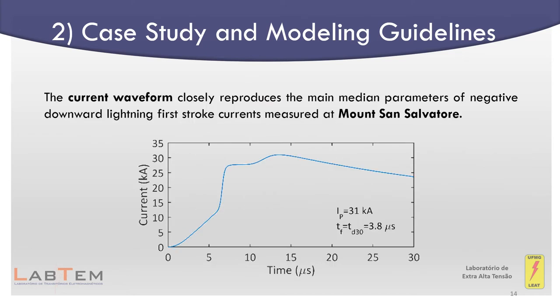The current waveform shown in the figure has been adopted in the simulations. This waveform closely reproduces the main median parameters of negative downward lightning first stroke current measured at Mount San Salvatore. This waveform is modeled as the sum of Heidler functions. The first stroke current is characterized by a peak value of 31 kA and a virtual front time of 3.8 microseconds.